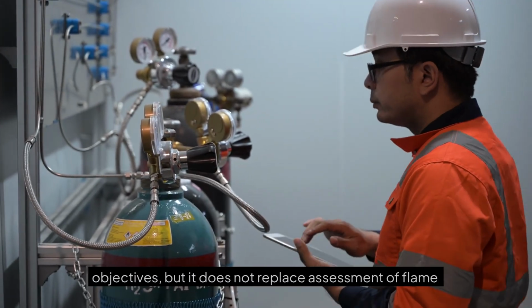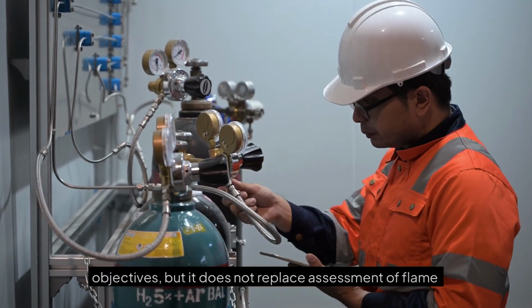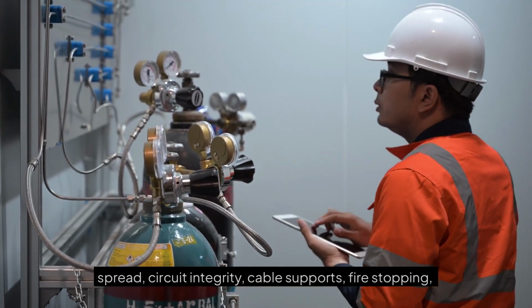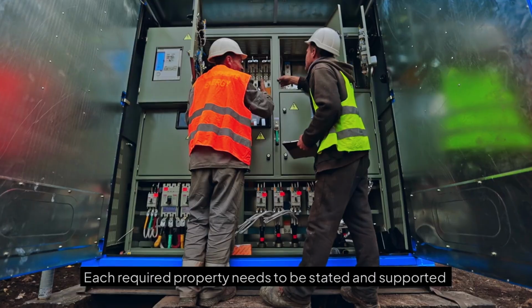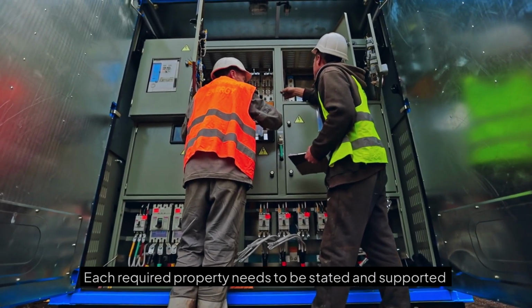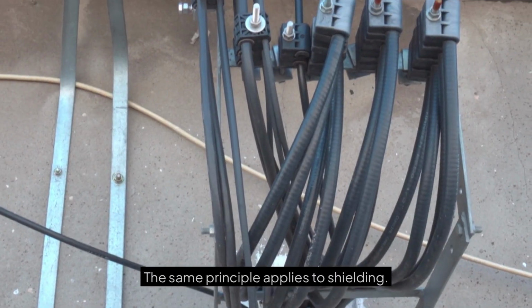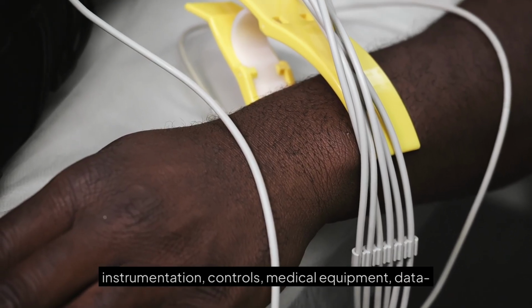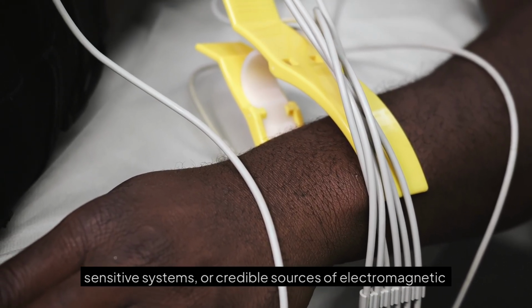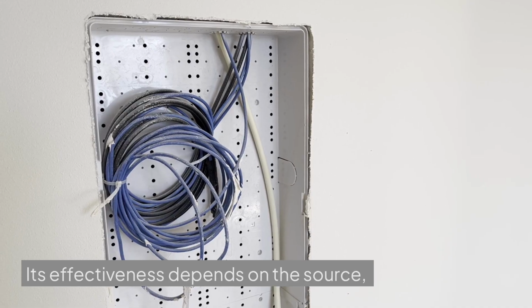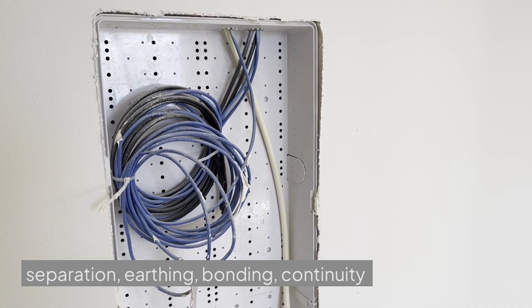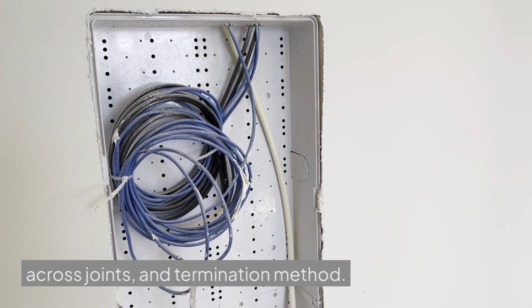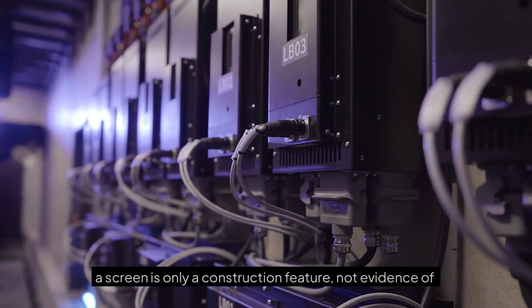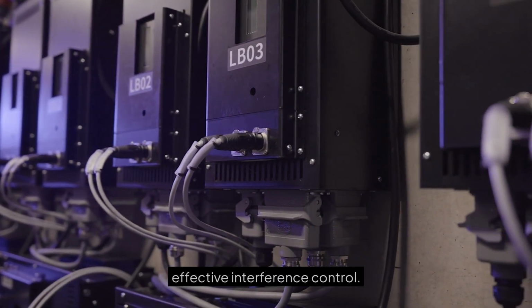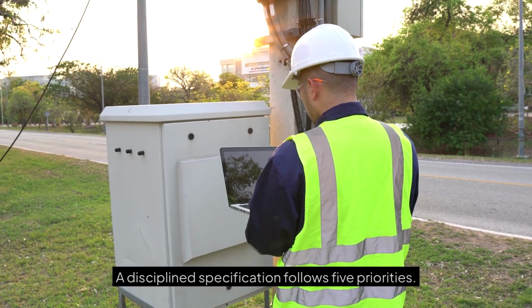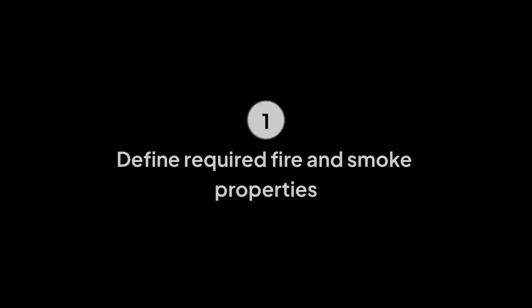effective interference control. A disciplined specification follows 5 priorities. First, define the required fire and smoke properties and the evidence supporting them. Second, establish the circuit function, including whether operation must continue during an event. Third, identify any credible electromagnetic source and victim path. Fourth, confirm that the cable can be installed and terminated correctly along the proposed route. Finally, maintain an evidence chain linking the delivered reels to the approved schedule.